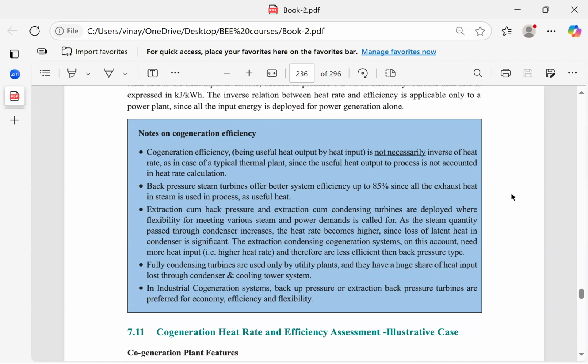Now, about cogeneration efficiency, how do we calculate it? By direct method: what is the total heat input by fuel burning? That is kilos of fuel multiplied by the calorific value of the fuel, which is the total input. What is the total output? That is the heat going to the process plus the heat going to electricity. So output divided by total input gives you the efficiency.